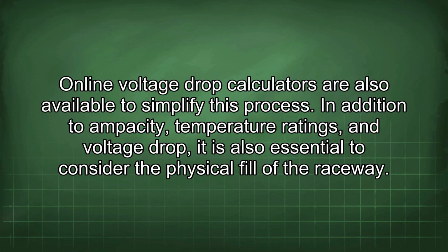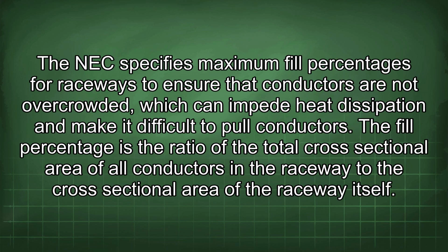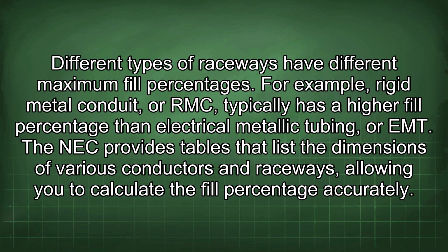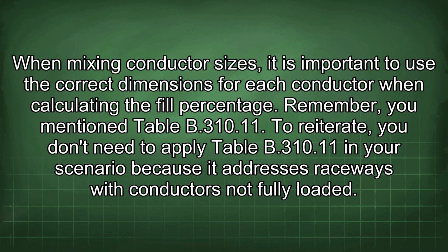In addition to ampacity, temperature ratings, and voltage drop, it is also essential to consider the physical fill of the raceway. The NEC specifies maximum fill percentages for raceways to ensure that conductors are not overcrowded, which can impede heat dissipation and make it difficult to pull conductors. The fill percentage is the ratio of the total cross-sectional area of all conductors in the raceway to the cross-sectional area of the raceway itself. Different types of raceways have different maximum fill percentages. For example, rigid metal conduit, or RMC, typically has a higher fill percentage than electrical metallic tubing, or EMT. The NEC provides tables that list the dimensions of various conductors and raceways, allowing you to calculate the fill percentage accurately. When mixing conductor sizes, it is important to use the correct dimensions for each conductor when calculating the fill percentage.